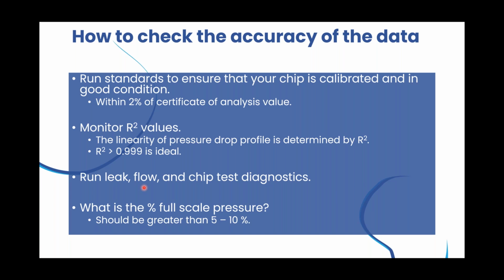This feature allows these instruments to perform unlimited measurements with small volumes and to recover the samples as well. For example, for recovering your sample, if you want to use it for another diagnostic test like DLS or SEC or whatever other technique you want to use. So let's go back to accuracy.